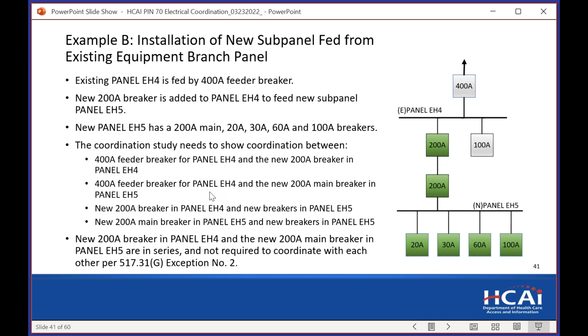For example B, we're adding a new panel. New panel is EH5. It's being fed from panel EH4 through a new 200 amp feeder breaker. The panel itself has a main breaker, and we have a 20, 30, 60, and 100 amp. Coordination study is going to need to show coordination of the 20, 30, 60, and 100 with the 200 main breaker and with the 200 amp feeder breaker. And it's going to need to show coordination of the 200s with the 400 amp main breaker.